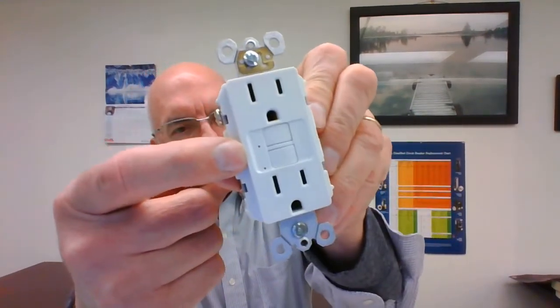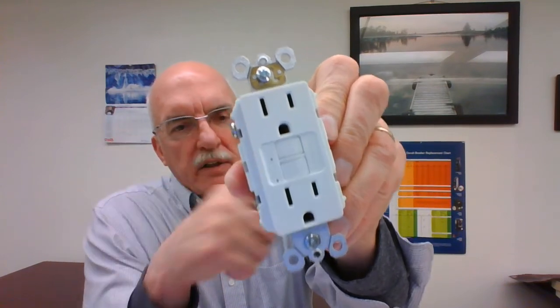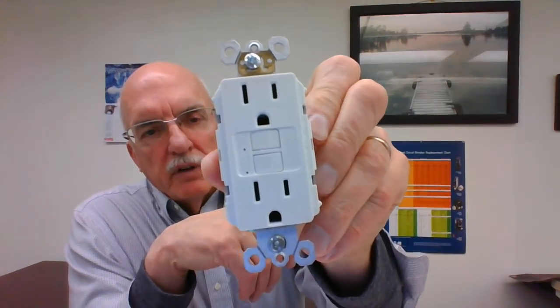So we could do the same thing with the dual-purpose receptacle outlet replacements. All right, this is a Legrand type receptacle, and it's got an AFCI and a GFCI, and it's got the two pilot lights there that will tell you the circuit is either on or tripped, whatever the manufacturer says in the instructions. And also, if you want to replace that two-prong receptacle with this, now you're given the AFCI and the GFCI, and you can replace the receptacles downstream, take the two prongs out, put three prongs in, and put the sticker on there that says GFCI protected, no ground.